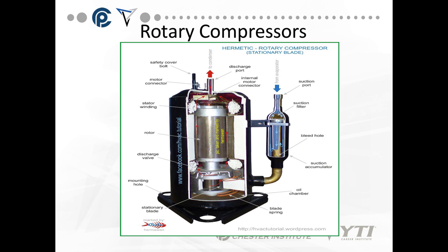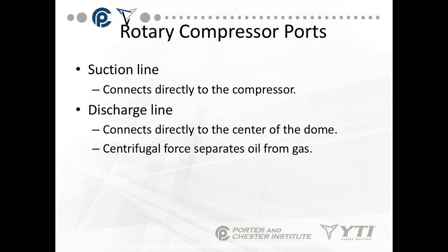The dome is on the discharge port — it is on the high side. The suction line comes in from the side at the bottom, and then the refrigerant is pushed through and out the top. The suction line connects directly to the compressor, and the discharge line connects directly to the center of the dome. The centrifugal force generated by the rotating rotor and blades separates the oil from the gas, so the majority of the oil actually stays in the compressor.